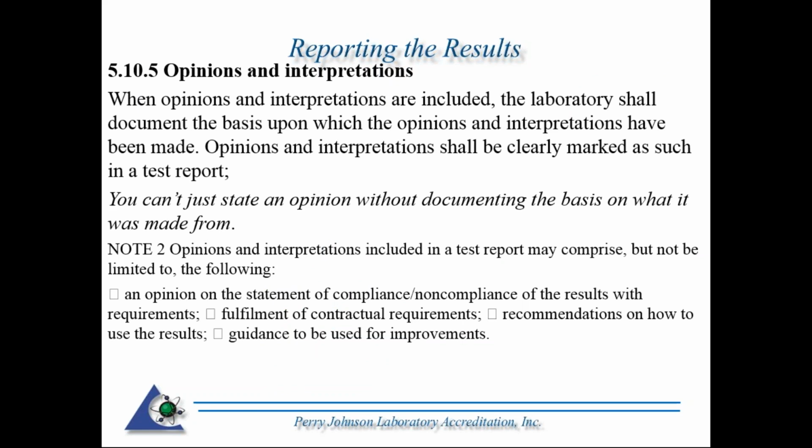Opinions and interpretations. This is line item 5.10.5. When opinions and interpretations are included, the laboratory shall document the basis on which the opinions and interpretations have been made. Opinions and interpretations shall be clearly marked as such in a test report. This is specified for test reports. You just can't state an opinion without documenting the basis on what it was made from.